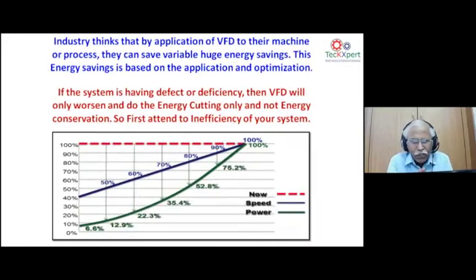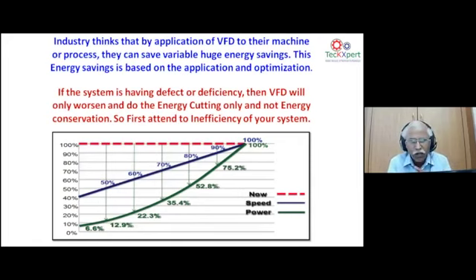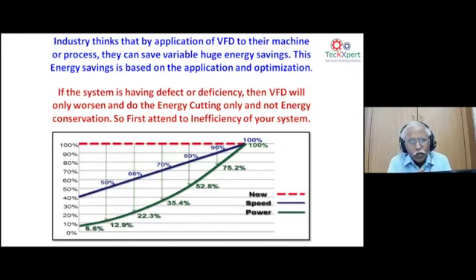The industry often thinks VFD is a cash cow for any system — but VFD is not a cash cow. VFD facilitates matching the utility to production requirements. Some textile mills claim 50–60% savings from a VFD on a 5.5 kW blower, but that's not realistic — the end-to-end static pressure for a given duct must be maintained.